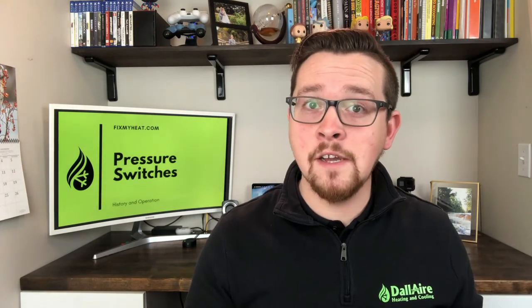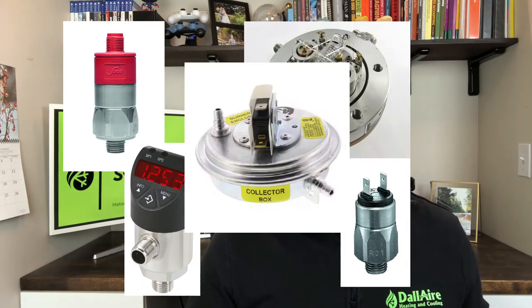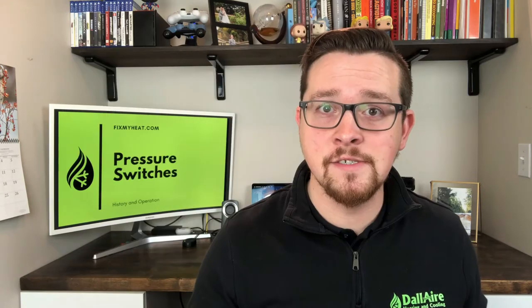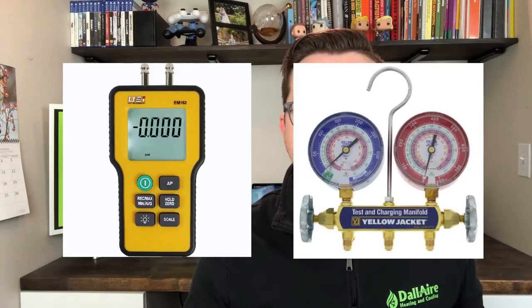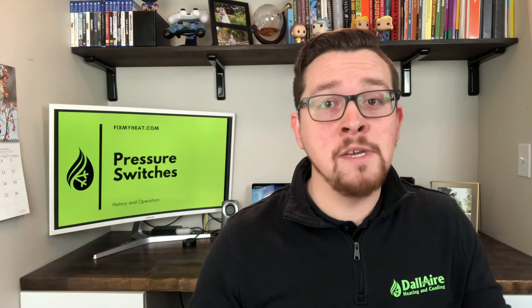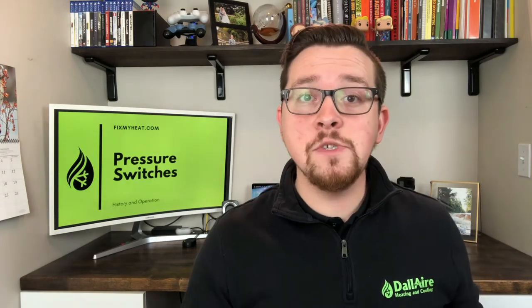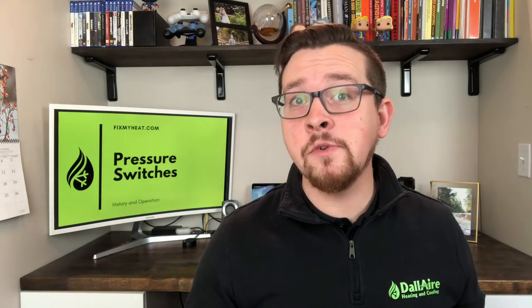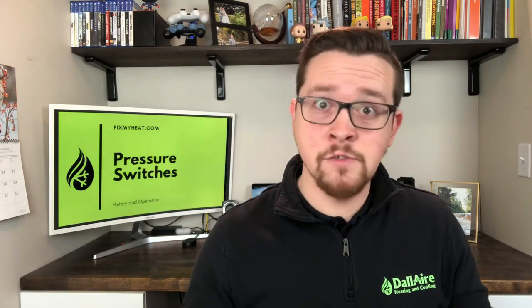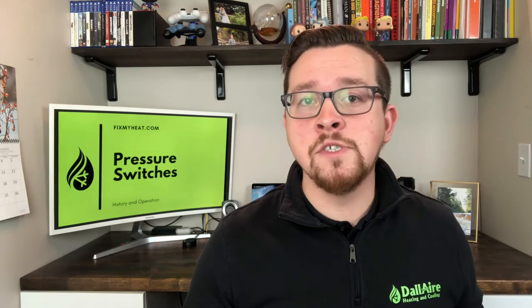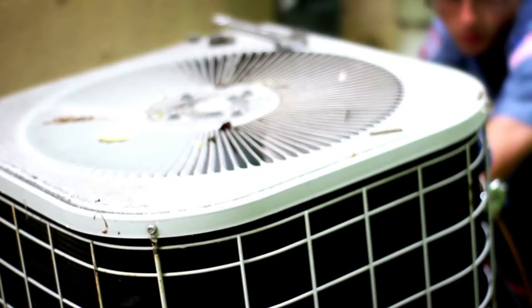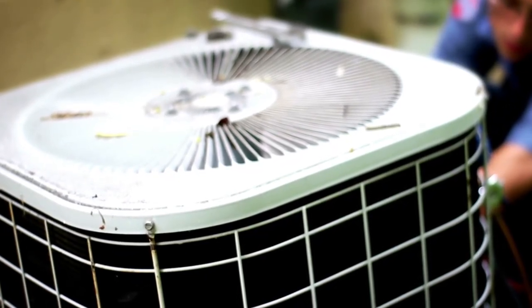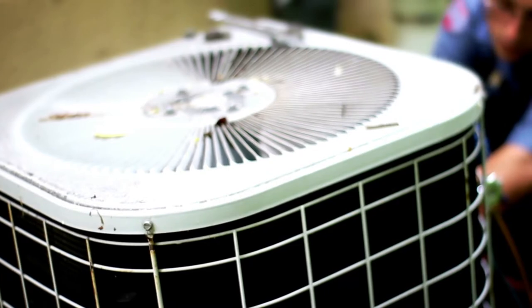Ultimately, throughout the 1900s, humans invented multiple renditions of mechanical and electrical actuating pressure switches. Also, manometers and refrigerant gauges, which are the tools that you'll need if you want to measure air pressure and refrigerant pressure. These switches can either close an electrical circuit during a rise or fall of pressure, or they can open an electrical circuit in those same circumstances. Normally open pressure switches are commonly used on gas furnaces and some humidifiers. Normally closed switches are generally used as safety devices, like drain monitors and refrigerant pressure monitors.